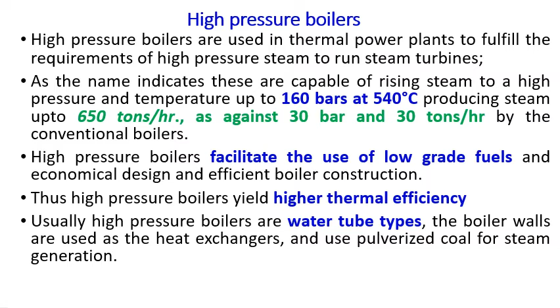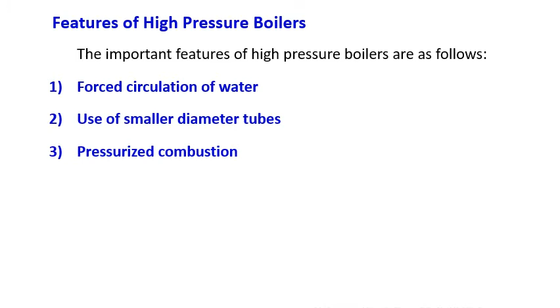The features of high pressure boilers. The important features of high pressure boilers are the forced circulation of water, use of smaller diameter tubes, pressurized combustion, space area, and power output. Right, let us see what is meant by forced circulation of water. Since the pressure inside the high pressure boiler is very high, generally we use only one pump, the feed pump, that is called the feed water pump, to pump the water. After that, the action takes place due to buoyancy force or density, therefore we don't want forced circulation in the conventional boiler. But in this type of high pressure boiler, we want forced circulation.